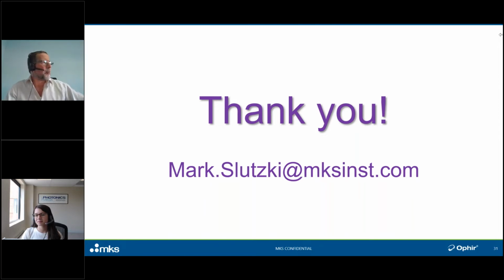That's actually a good question. I was about to say that in sensor specifications, it's probably there, but the truth is no, I don't think it is. We have on our website at Ophir, we talk about that in one of the FAQs, but we all know that that's not in anybody's face when they're looking for a particular sensor. So it depends on the absorber type. For the kind of absorbers that we're talking about here, the angle dependence is not zero, but it's generally pretty small. It's probably negligible out to incident angles of even up to a few tens of degrees from normal.